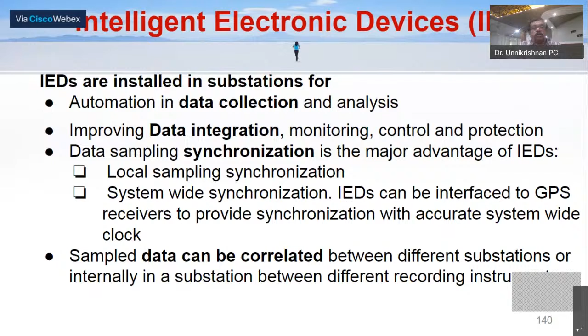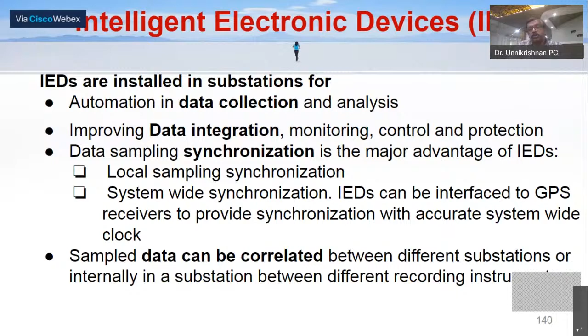So you can have a local sampling synchronization, and also you can have a system-wide synchronization. That is, an IED located in Kerala and an IED located in another state can be synchronized. They may be running with the same clock. So a system-wide synchronization is also possible by using IEDs. This is done by connecting IEDs to GPS receivers and satellites. And the sample data can be correlated between different substations. This correlation is possible only if we are using a common time reference, that is synchronization. Otherwise correlation is not possible.